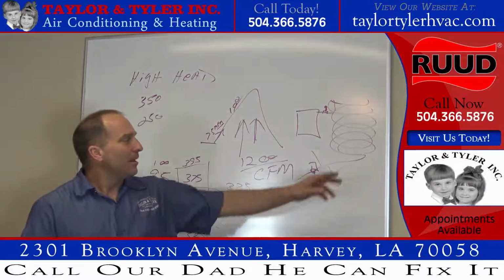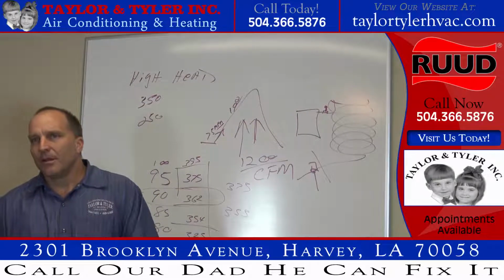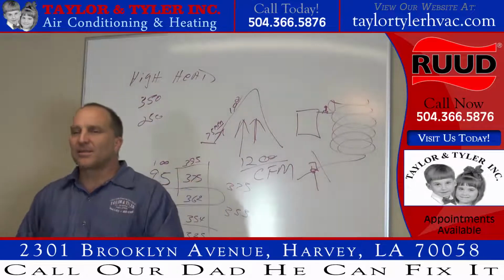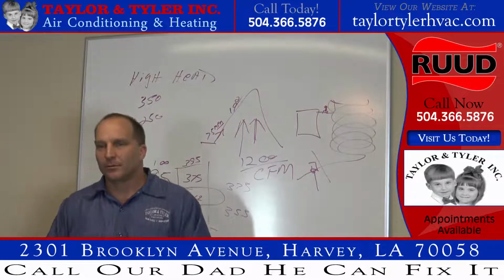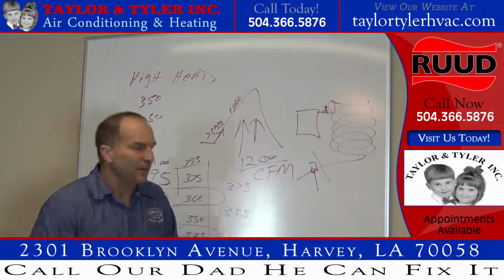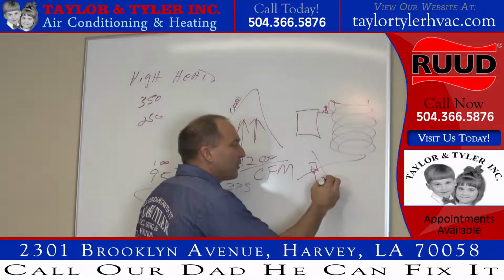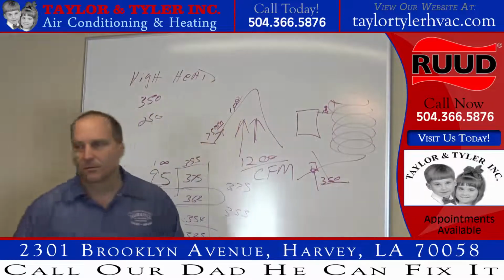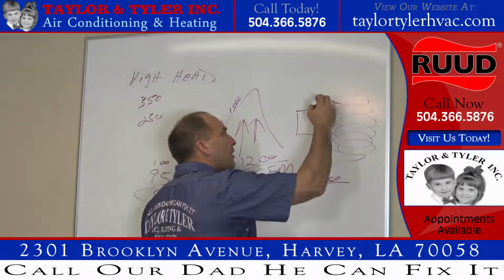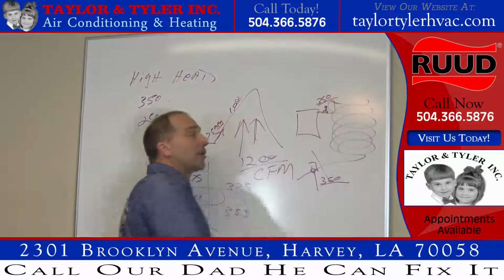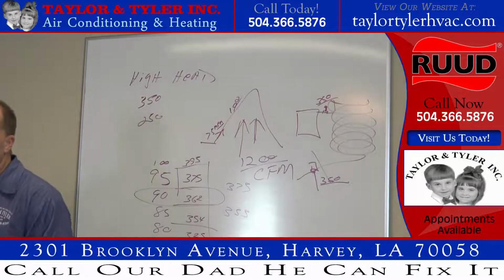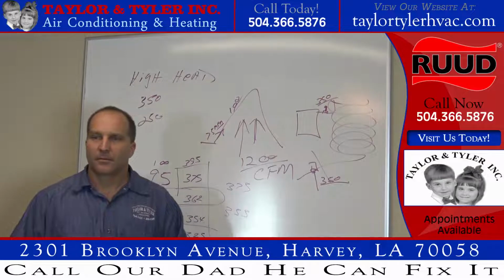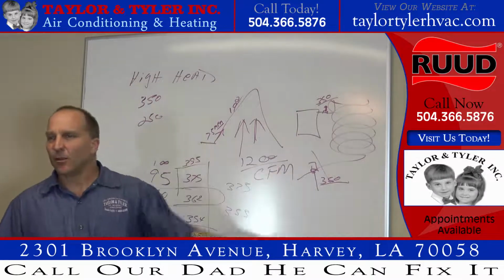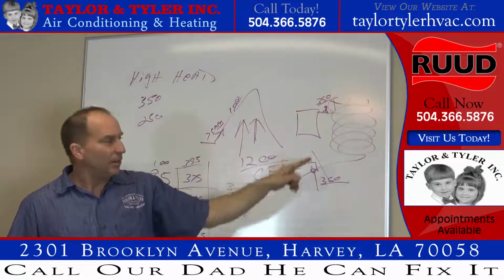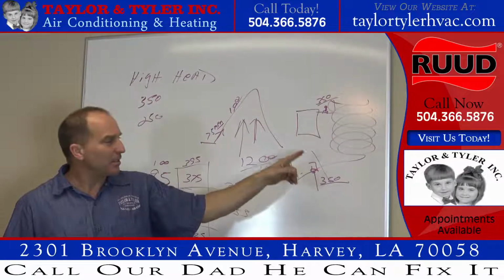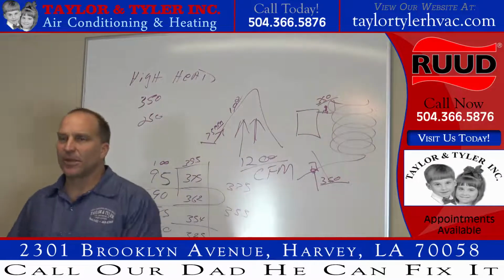Okay? Now, on a normal operating system, if my head pressure is 350 pounds right here, what is my head pressure here? 350 pounds. But wait a minute. That's a hot gas line. You can burn yourself on that one. You can't burn yourself on this one. How is it 350 here and 350 there? What's the answer to your question?